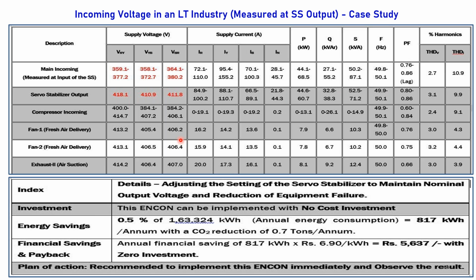they had some rectification problem in the transformer. So we insisted that the company check with an OEM and correct the voltage, because one phase is at a much higher voltage than the other 2 phases. There may be many problems. There may be a problem with that particular phase's wiring, crimping, or a loose connection.